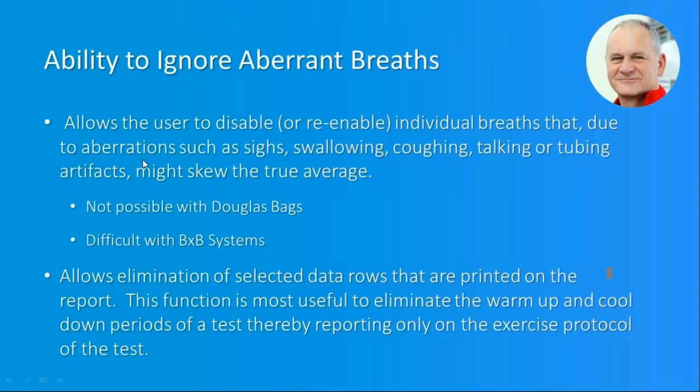One of the most important aspects of the MOXUS system is its ability to remove aberrant breaths or any data with issues. Aberrant breaths would include sighs, swallowing, coughing, or other real-life value issues that occur when measuring people. This is impossible with Douglas bags, where all of the sample is taken into the bag, and is very difficult with breath-by-breath systems. The MOXUS system allows you to eliminate rows of data you don't want to include because you can see they have issues.